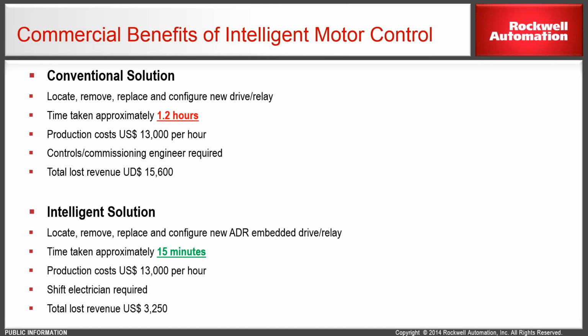When it comes to the intelligent solution, the location of the fault, replacement and configuration is quite easy because it is all connected on Ethernet, so you are aware of exactly where the fault occurred. If any replacement is required, you can immediately replace it. There is no reconfiguration required of the device because of ADR functionality, and it is done in just 15 minutes. Even a shift electrician can do it, and the total lost revenue is significantly reduced, approximately 25% of what you have in conventional solutions.